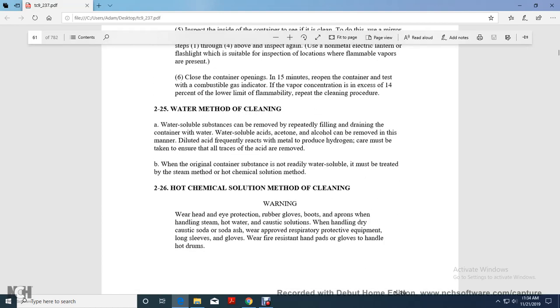225. Water method of cleaning. Water soluble substances can be removed by repeatedly filling and draining the container with water. Water soluble acid, acetone, and alcohol can be removed in this manner. The dilute acid frequently reacts with the metal, producing hydrogen. Care must be taken to ensure that all traces of the acids are removed. If the original container substance is not readily water soluble, it must be treated by the steam method or the hot chemical solutions method.